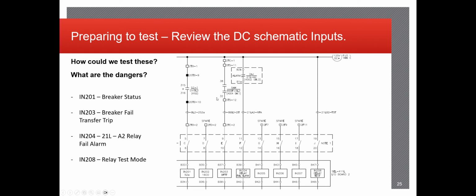But if you run into anything prior to operating this and testing the input, you always want to report it to the client and say, hey, do you want us to do this? Or just give them options. Like, we can test this, but we need to open its A, B, and C, and we need to kill the communications to this other site. Just coming up to them and saying we can't do this isn't usually a good option, because they don't like hearing that. But coming up to them and saying we can't do this right now, but these are our solutions, is a much better way of approaching it.